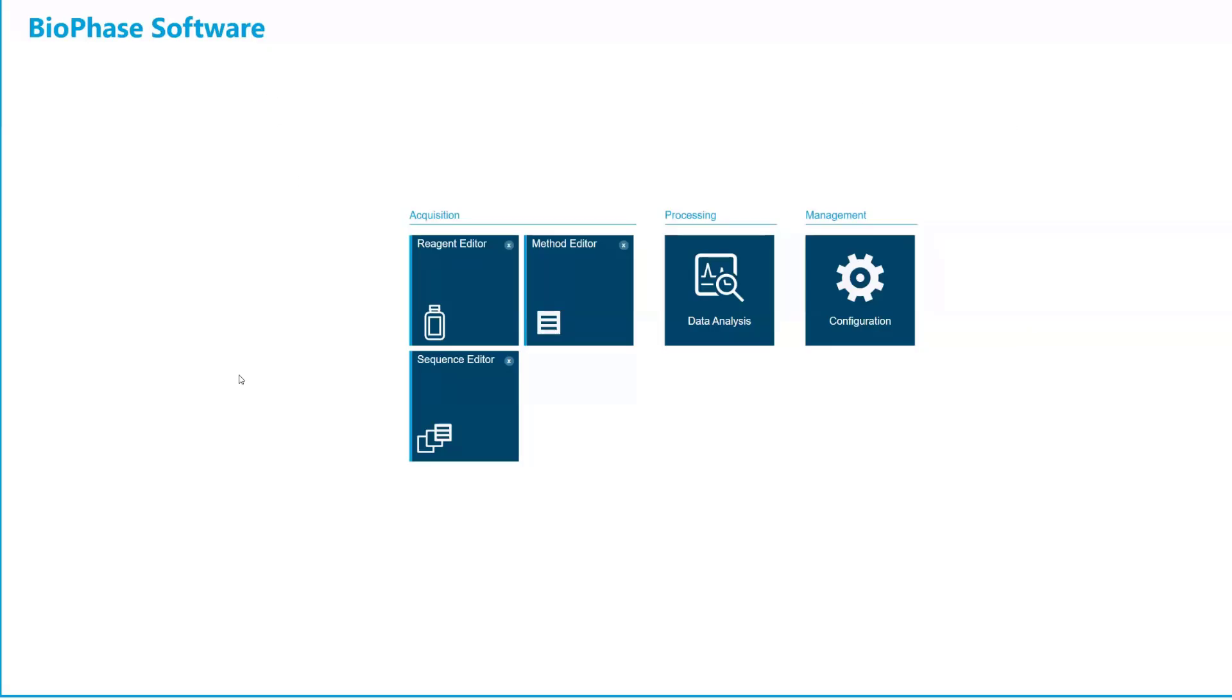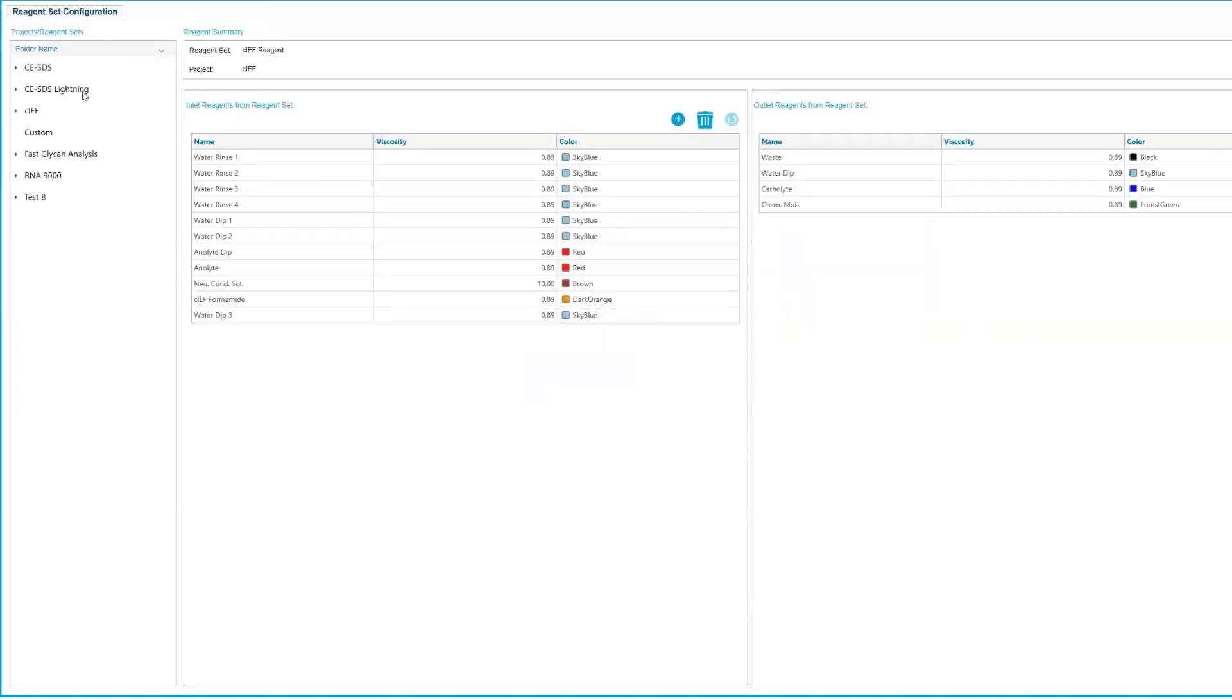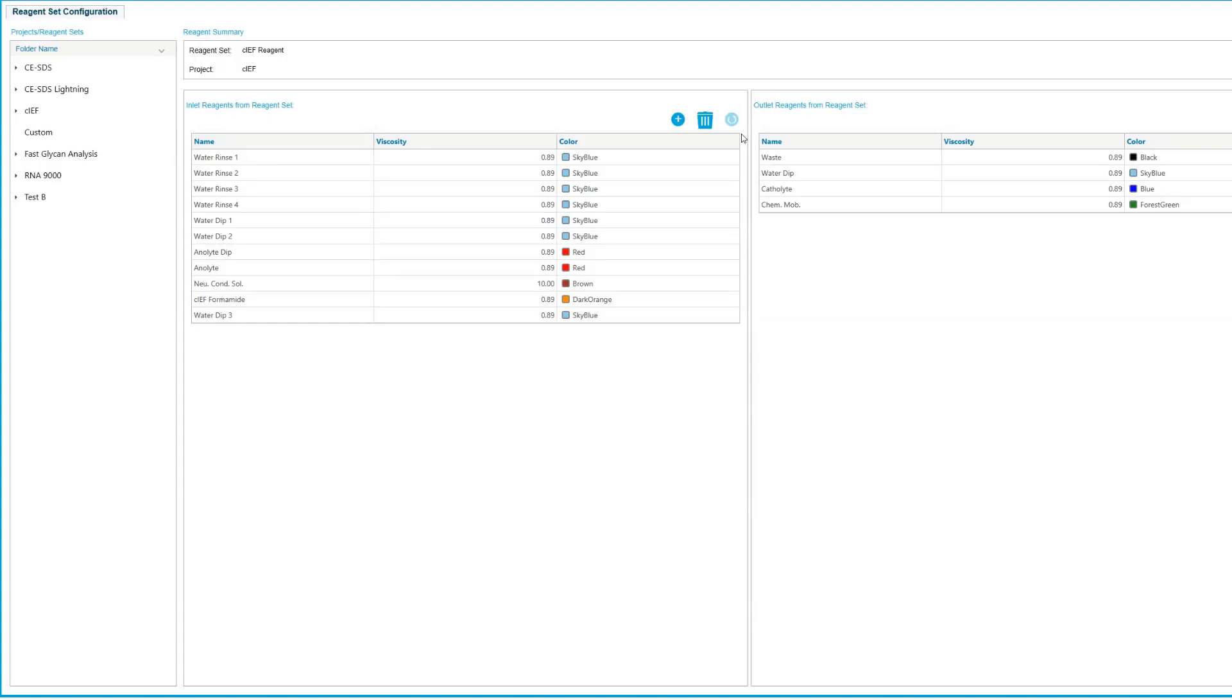This is a look at the BioPhase software. It has a number of different tiles here. Where we start in our workflow is very sequential and will certainly make sense. We start with our reagent editing. I already have the CIEF reagents opened up. What we're going to do is add all the reagents that we ever want to use on either the inlet side of our capillary or the outlet side of the capillary. These are now dynamic. On the PA 800 Plus, we're really designating a location for those reagents to go. But on BioPhase, we've made this more dynamic. We just say list whatever it is you want to use, and later on we can choose where it's going to go.